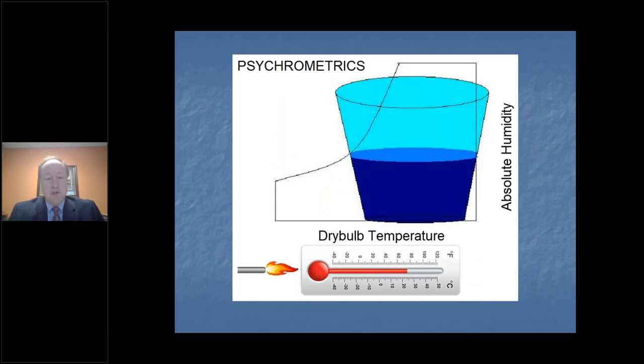I also have another simple chart here. I think of this psychrometric chart as a bucket of water, and I've overlaid a bucket or a pail here to help you understand that. There are two things that I'm concerned about with the chart. There's a lot of information on it and it's very useful, but the two things that I think of primarily are the dry bulb temperature and the dew point temperature. I want to know how much heat I have in that particular air and how much moisture I have. So if I'm adding a flame or adding some heat into the facility, think of the thermometer going from left to right.